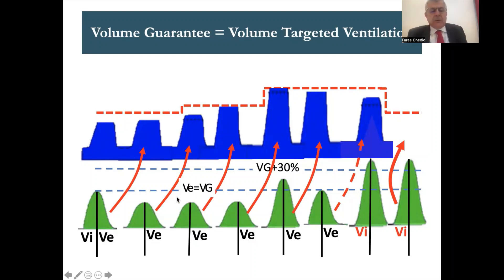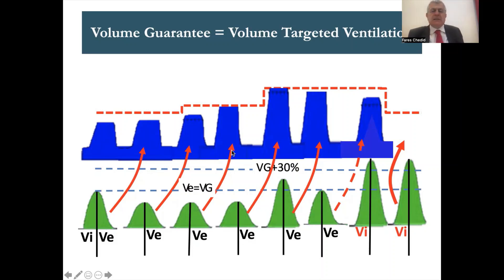We compare the volume expired to the target volume. If the expired volume equals the target, the next pressure will be the same as the previous one. If the volume produced was below the target, there will be an order for the PIP of the next breath to go up, but it cannot exceed the PIP max. The PIP max is set 3 to 5 above the PIP measured on the patient for safety. When we reach the PIP max, we cannot increase the volume further unless the clinician increases the PIP max.